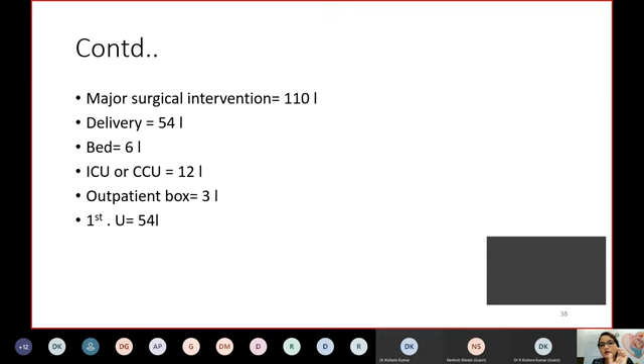So now how do we do the calculation? I told you that I've got this 250 bed hospital, and for every bed, as mentioned in the previous slide, it is 6. So 250 multiplied by 6 is 1500. Similarly, for 30 surgeries a day, and for every surgery you require 110 liters, your number is 3300. For 40 deliveries, for one delivery you require 54, so 54 into 40. Similarly, we've totaled everything up, and it comes out to 7230 liters per day. And as I said, you can take a 15% extra margin, so the total will come up to 8320 liters.